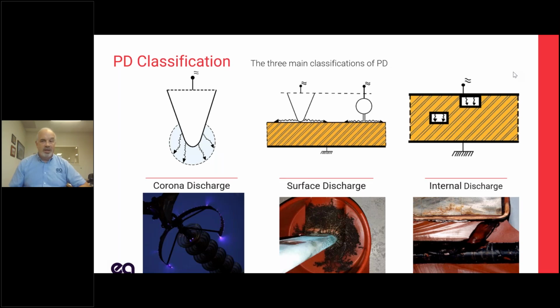Internal discharge, on the other hand, is the slowest moving and hardest to find, but it can take years or decades to lead to failure. So this is where the discharge is actually through the insulator. It's a completely contained void inside an insulator, and that would eventually grow to the point where it would catastrophically fail. And you can see in that picture that channel that's eaten through that insulator. So that's an insulator that's been cut in half, and you can see that channel that's eaten through it.